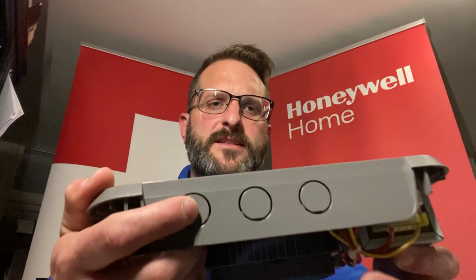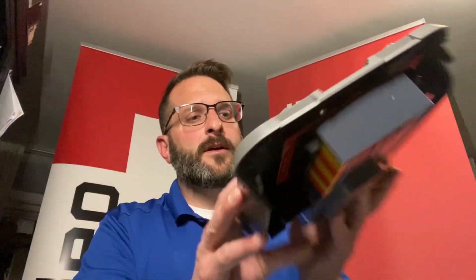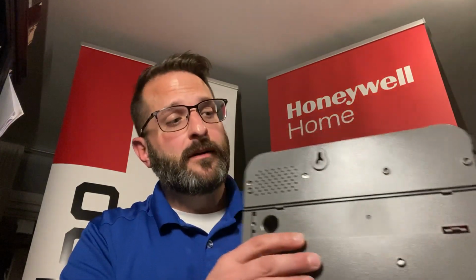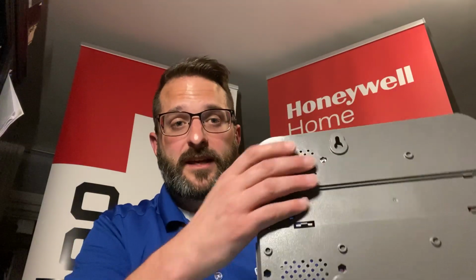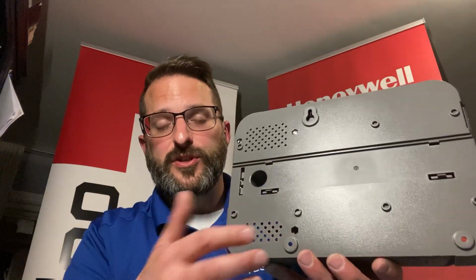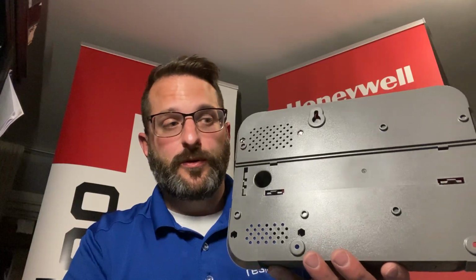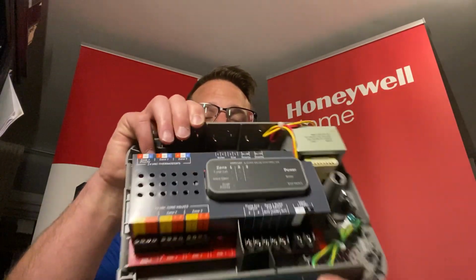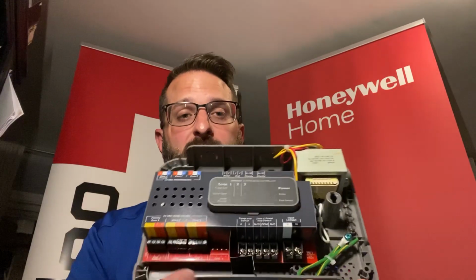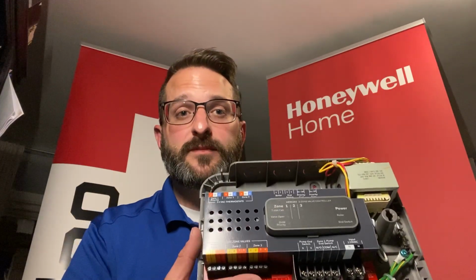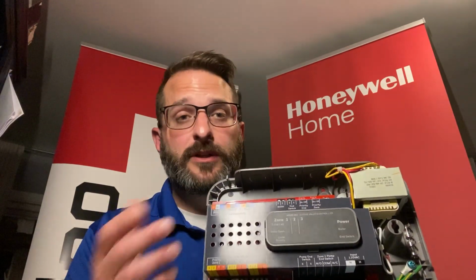The knockouts are really easy to come out. You can just pop them out with your finger. We can support DIN rail, it pops right on the DIN rail, and then we have a self-leveling screw hole here. So just one screw, hang it, and then you can finish off mounting on the bottom here with those 2 screw holes. So that is the zone valve control. Again, the 5 and the 6 zones come with dual transformers. So we have 2 40 VA transformers, so 80 VA there. So plenty of power.